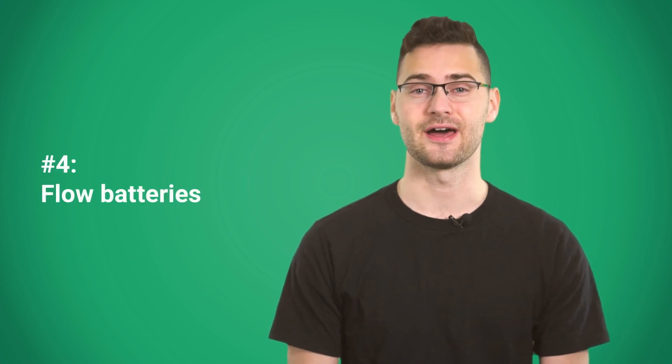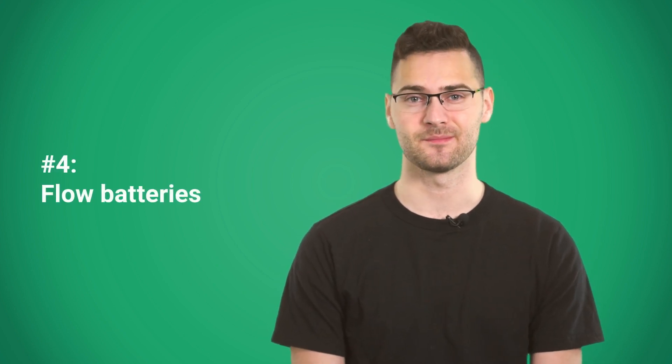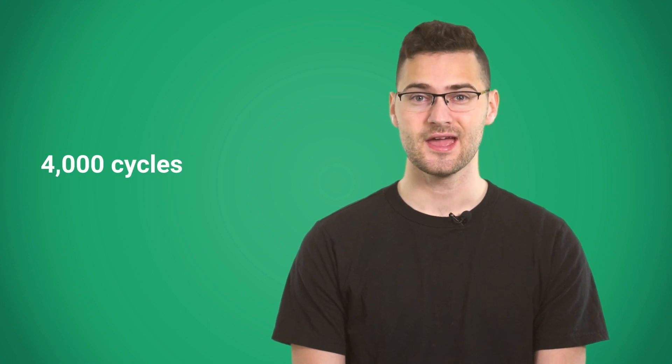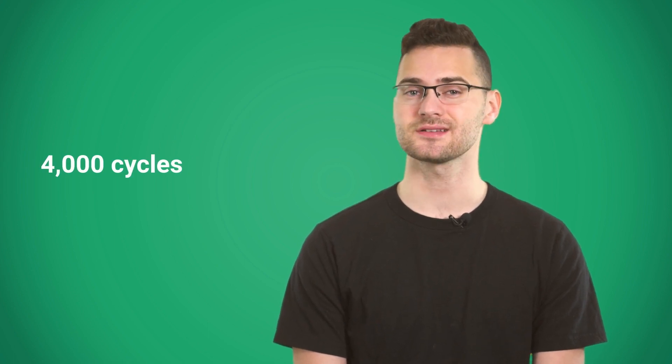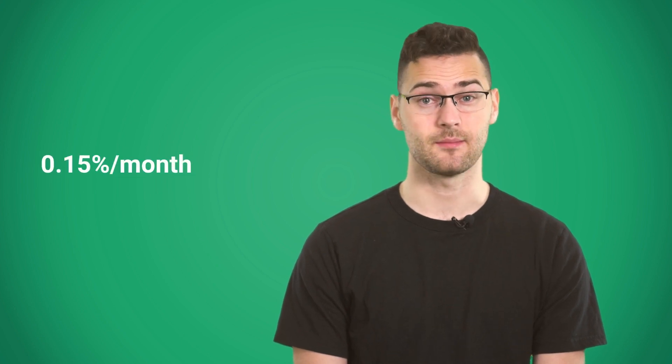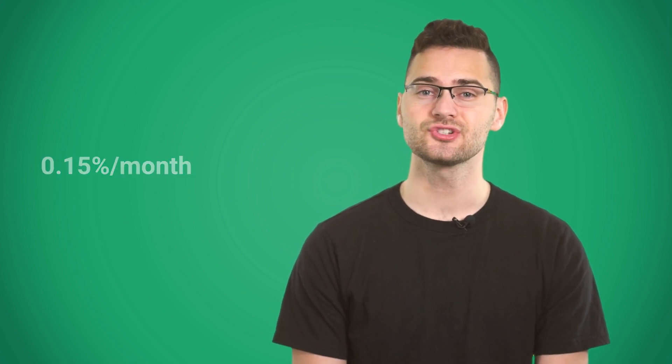The fourth type of battery is a flow battery. There's a lot of good things about them. You can discharge flow batteries fully, and they can stay empty for decades. A flow battery has a good lifespan around 4000 cycles. They don't need any maintenance, and their self-discharge rate is only 0.15% a month. They can store large amounts of power, which makes them good for off-grid systems.